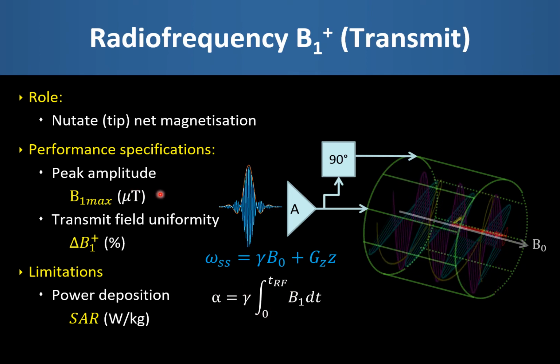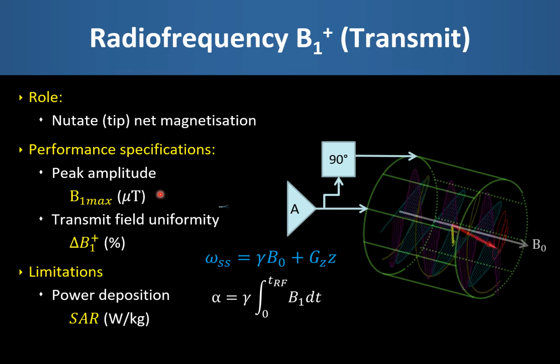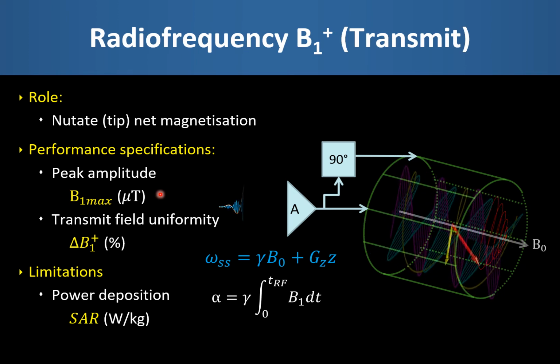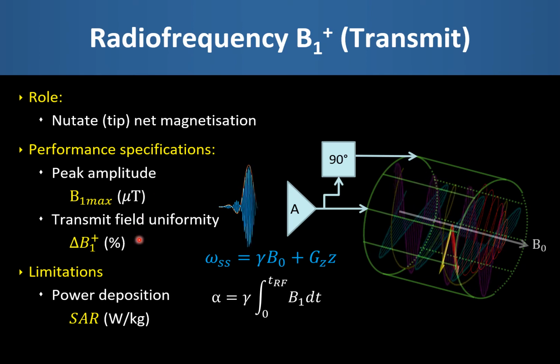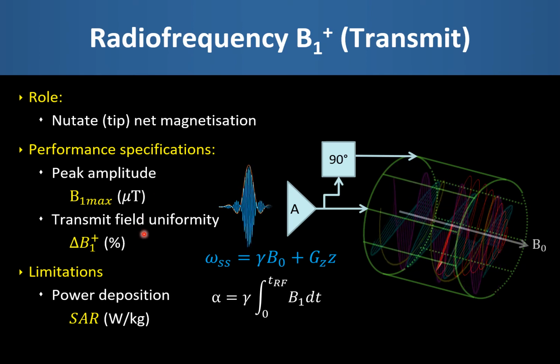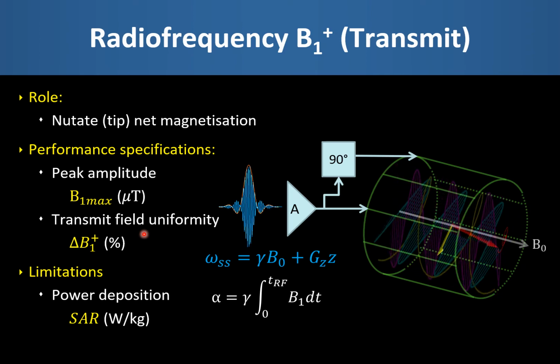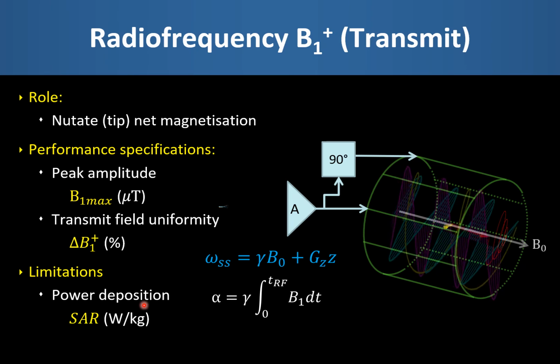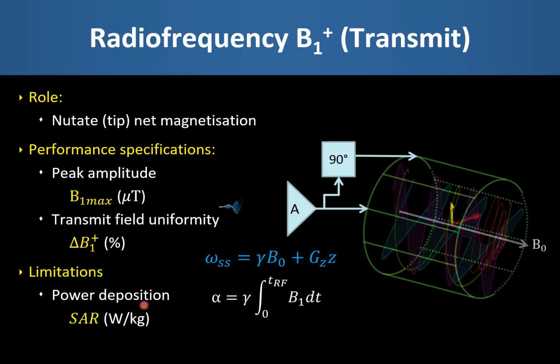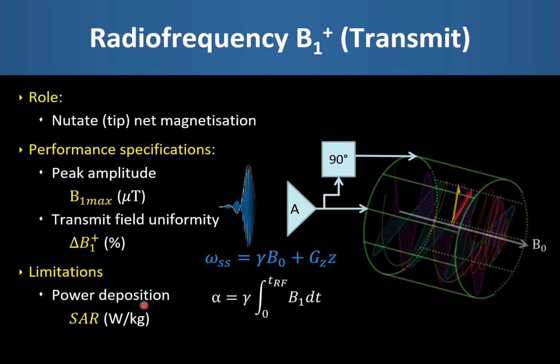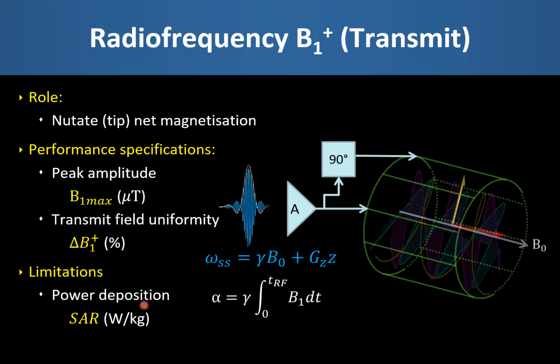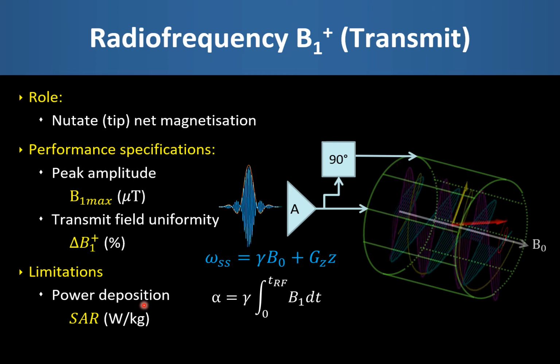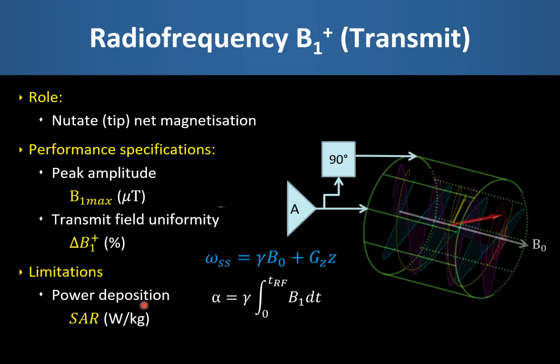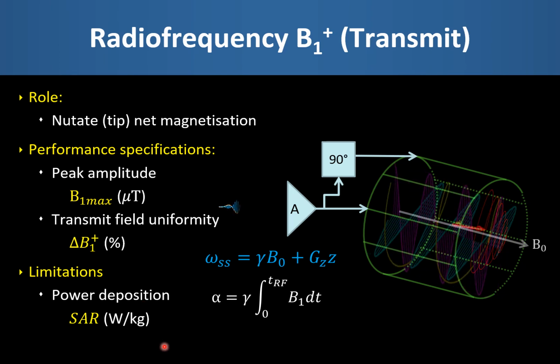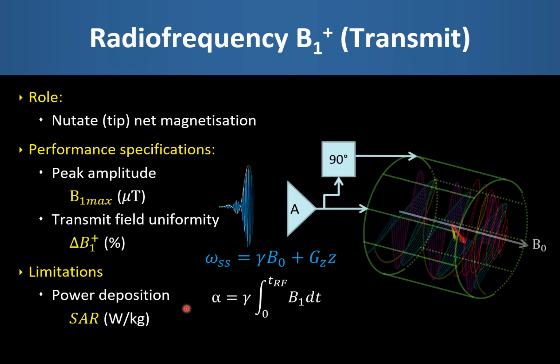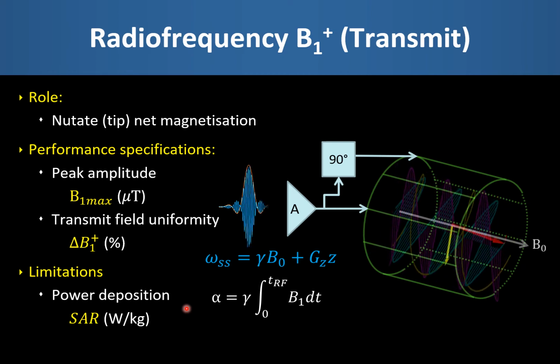In terms of performance specifications, the system is characterized by the peak RF amplitude that is available in terms of microtesla, and the uniformity of the transmit field within the coil, which can be expressed as a percentage of the nominal flip angle. The main limitation of the RF system is in the maximum power that can be deposited in the patient, because of the eddy current induced heating in the conducting tissues caused by the B1 field. This power deposition is known as the specific absorption rate, or SAR, and is limited as part of the MRI system specification. We shall discuss SAR in more detail later.